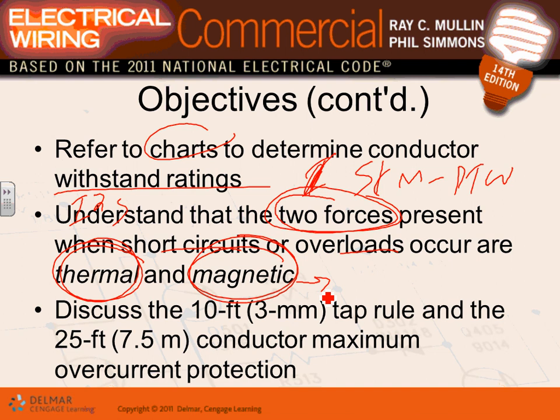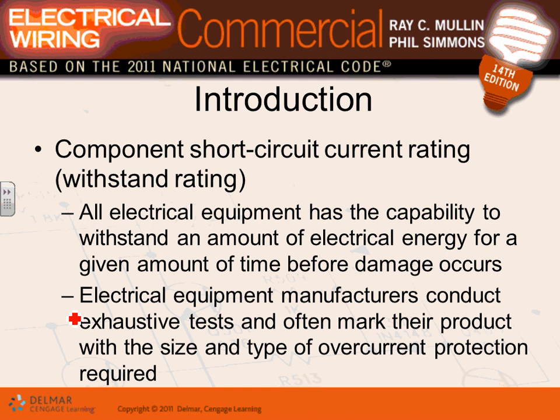The shaking happens with I peak squared, I believe. I peak is the peak of the signal that starts shaking the equipment. So anyway, you'll see it in a second. The last thing we're going to talk about is the tap rules, in particular the 10-foot tap and the 25-foot tap. Tap rules apply when you tap a conductor and put an overcurrent device larger than the conductor can handle. So that's basically what we're going to be talking about.